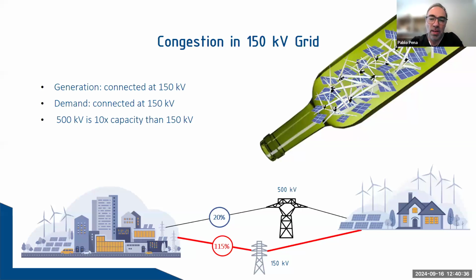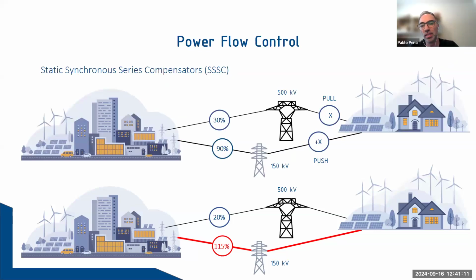Another problem we face in the grid is the congestion in the 150 kilovolt grid, where both the generation and the demand are primarily connected, and which leads to congestion in the high voltage grid. However, the extra high voltage system has 10 times the capacity of the high voltage network. There are some promising solutions for reducing congestion.